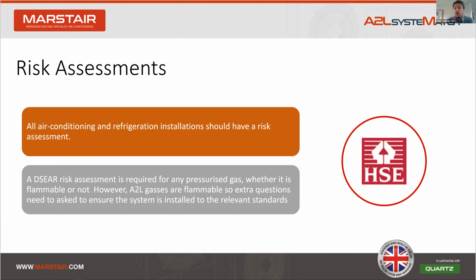Risk assessments. All current refrigerants are pressurized and have a toxicity level, so should have a risk assessment. However, with flammable refrigerants this becomes even more important. So we've worked with consultants and we provide a risk assessment template within our instructions to guide installers.